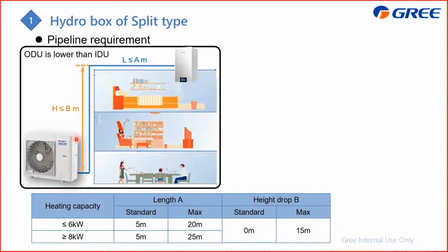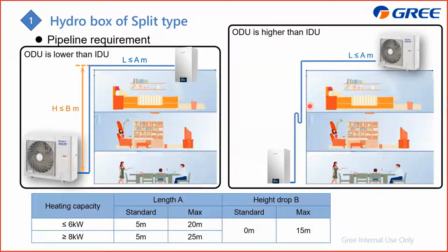To consider the indoor unit and outdoor unit, this case is for the split type. You can find that if the outdoor unit is lower than the indoor unit, there's no special requirement. Just ensure the total length is less than the requirement. But if the outdoor unit is higher than the indoor unit, besides following the requirements of the maximum height drop and the maximum distance, also for the height, at 5 to 7 meters, we require an oil trap. This is for the oil return.